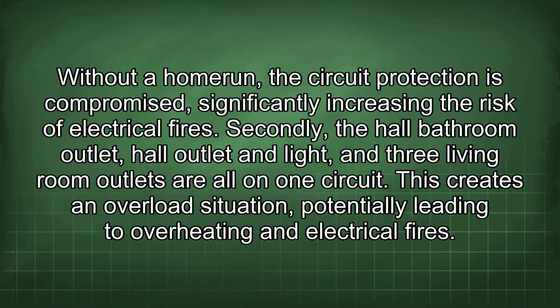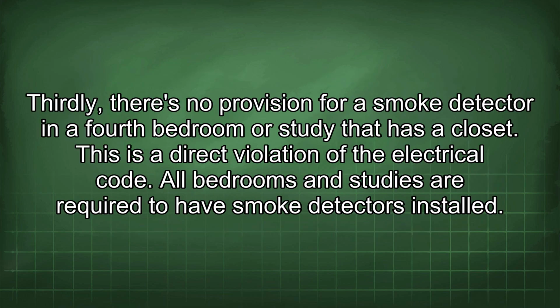Secondly, the hall bathroom outlet, hall outlet and light, and 3 living room outlets are all on one circuit. This creates an overload situation, potentially leading to overheating and electrical fires. Thirdly, there's no provision for a smoke detector in a 4th bedroom or study that has a closet. This is a direct violation of the electrical code. All bedrooms and studies are required to have smoke detectors installed.